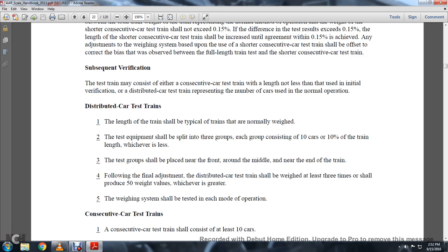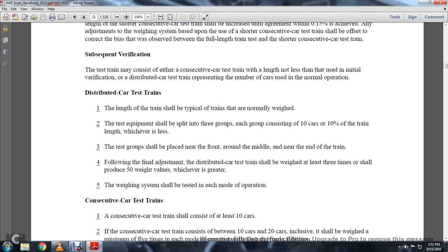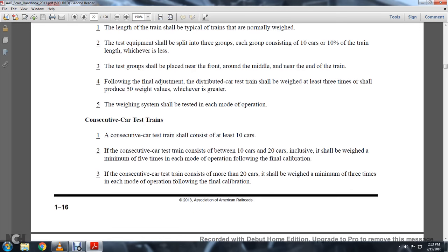Distributive car test trains: the length of the train shall be typical of trains that are normally weighed. The testing equipment should be split into three groups, each group consisting of 10 cars or 10% of the train length, whichever is less. The test groups shall be placed near the front, in the middle, and near the end of the train. Following final adjustment, the distributive car test train shall be weighed at least three times, producing at least 50 weight values, whichever is greater. The weighing system shall be tested in each mode of operation.